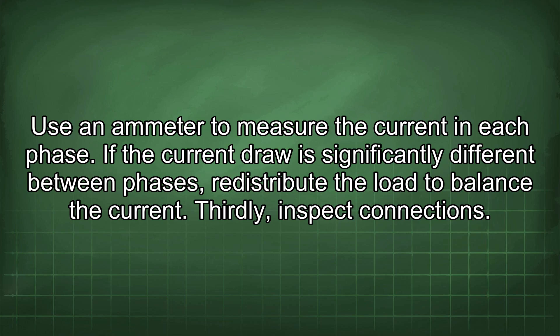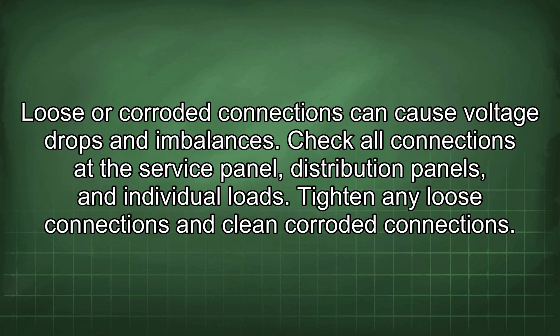Third, inspect connections. Loose or corroded connections can cause voltage drops and imbalances. Check all connections at the service panel, distribution panels, and individual loads. Tighten any loose connections and clean corroded connections.